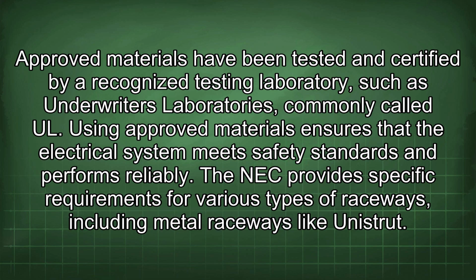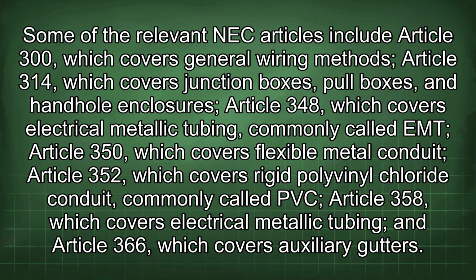The NEC provides specific requirements for various types of raceways, including metal raceways like Unistrut. Some of the relevant NEC articles include Article 300, which covers general wiring methods, Article 314, which covers junction boxes, pull boxes, and handhole enclosures, Article 348, which covers electrical metallic tubing, commonly called EMT, Article 350, which covers flexible metal conduit, Article 352, which covers rigid polyvinyl chloride conduit, commonly called PVC, Article 358, which covers electrical metallic tubing, and Article 366, which covers auxiliary gutters.